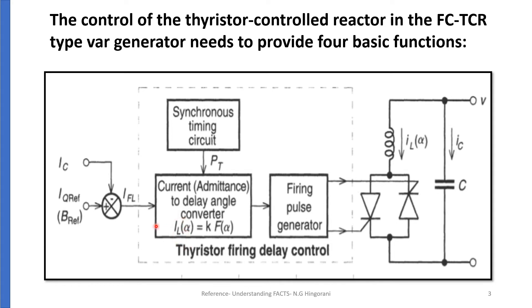This current we get from the FCTCR — it tells us the capacitive current and the required reactive reference current. This current minus that current gives us the fundamental current required for TCR operation, which gives us the alpha requirement. This is then given by the firing pulse generator to the TCR.